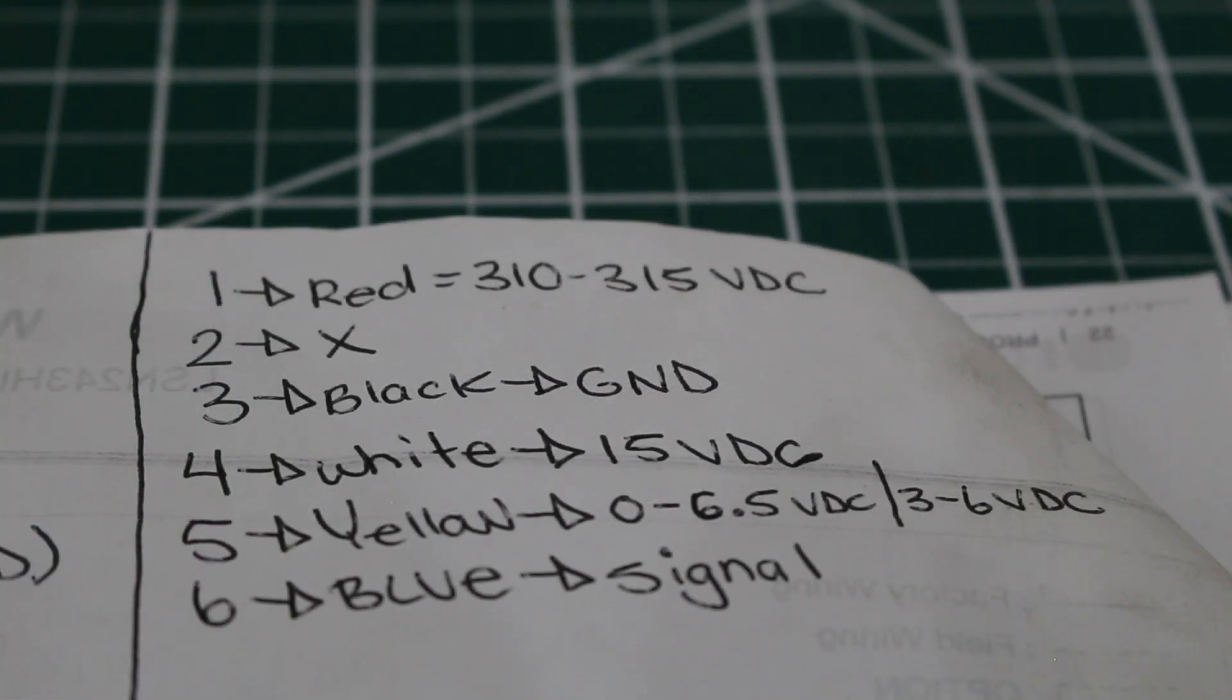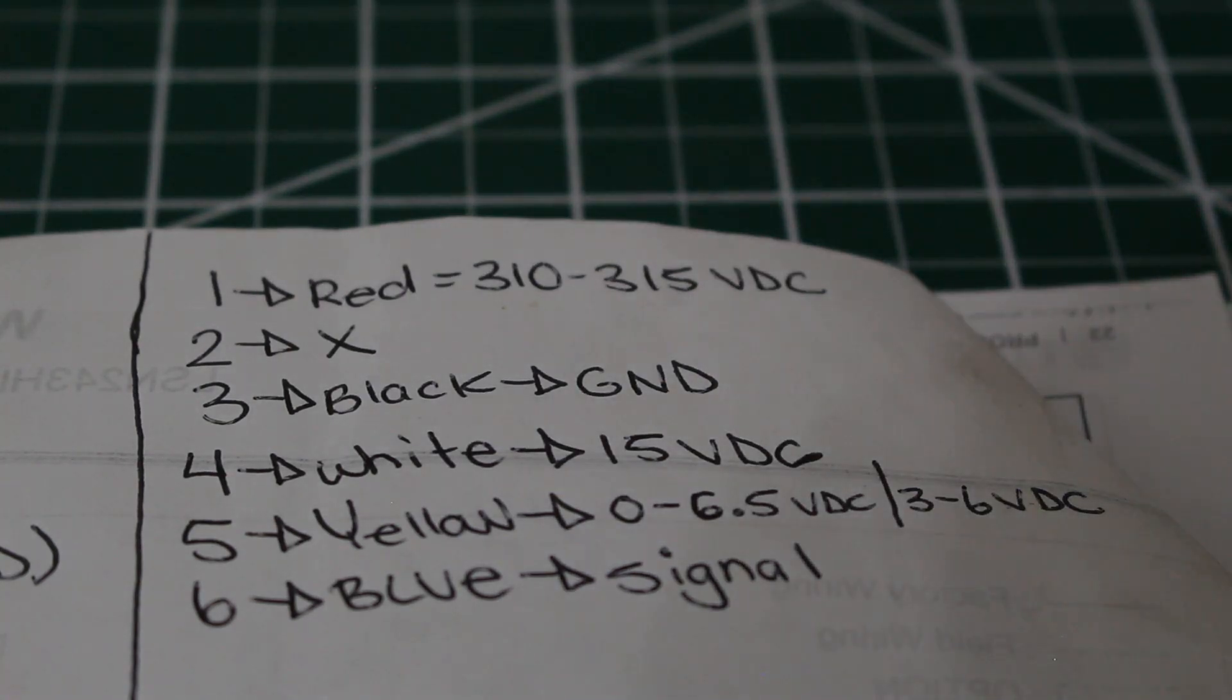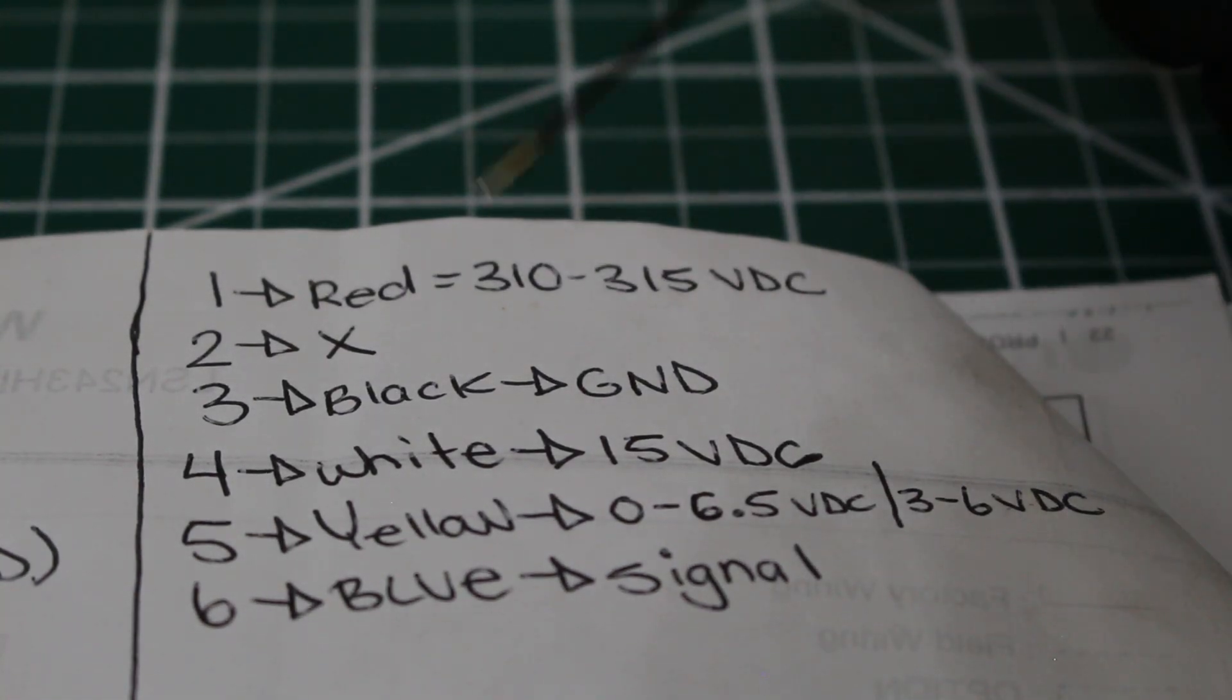This is how you would check the voltage. So black is always going to be your reference point. So that is terminal 3. So you're going to check from terminal 3 to 1, 3 to 4, 3 to 5, 3 to 6. So first off, 1 to 3, which is going to be your red. So between red and black, you should have your voltage. Remember, you're checking volts DC. So you should be getting 310 to 315 volts. That's typical of what these motors run.